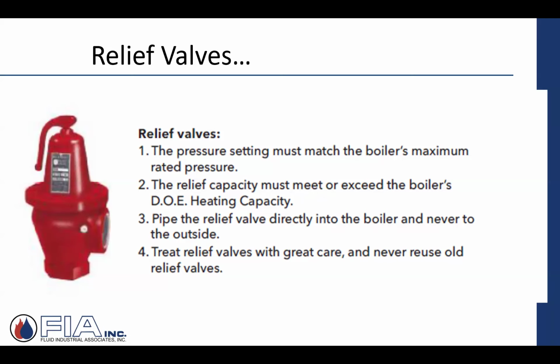So when the relief valves are selected, typically the appliance manufacturer a lot of times provides it. Sometimes it needs to be purchased separately. But these are two important criteria: what's the pressure rating, and then what's the heating capacity? Those are two important numbers.